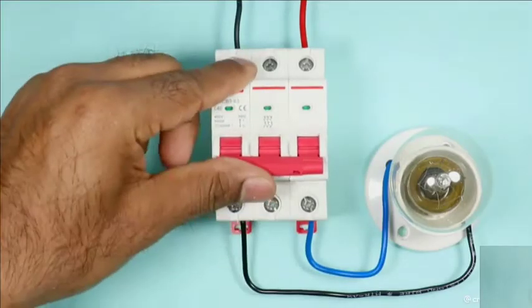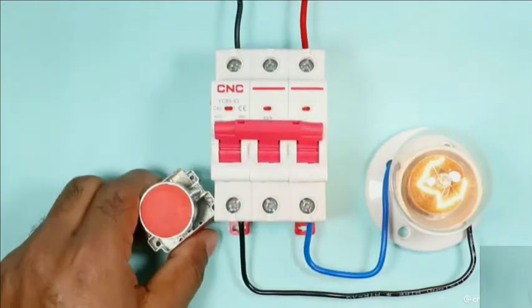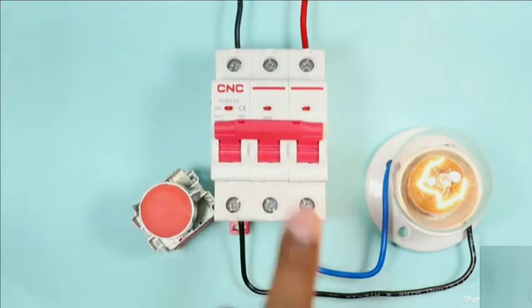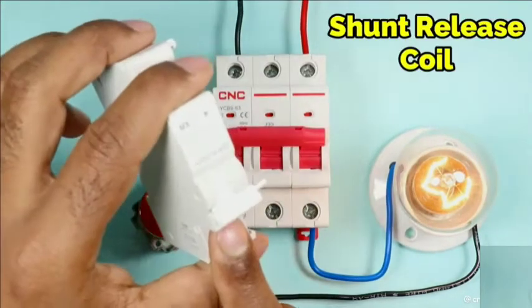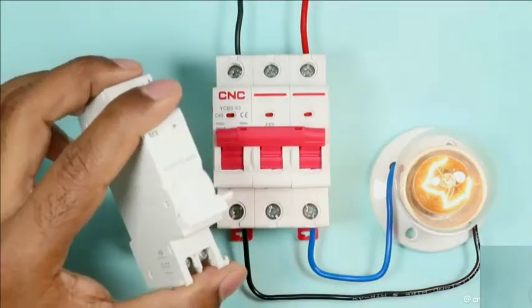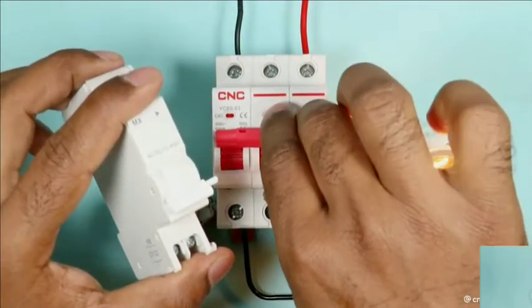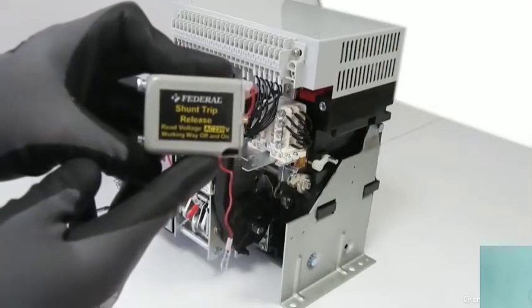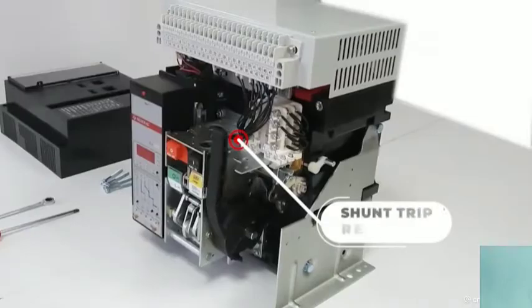If you want to turn off the MCB from a distance away, then by using push button you can turn off MCB, but you have to connect shunt coil with MCB through which we are going to turn off the MCB. If you disassemble the ACB breaker, you will find a shunt release coil through which we turn off the breaker.